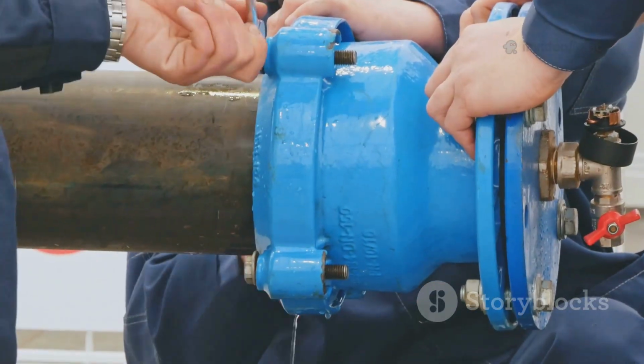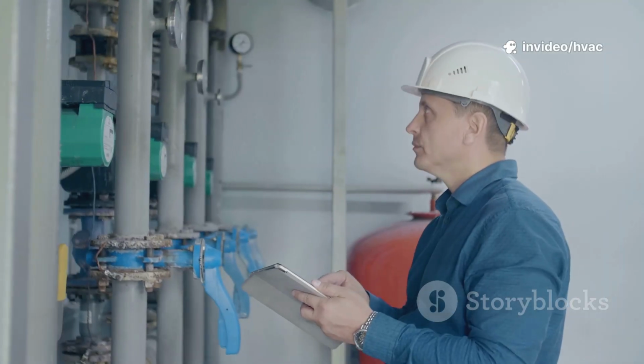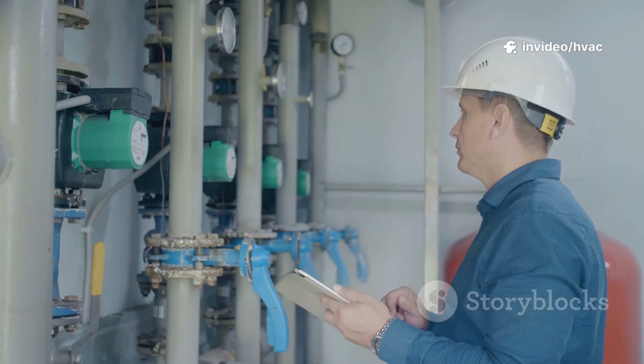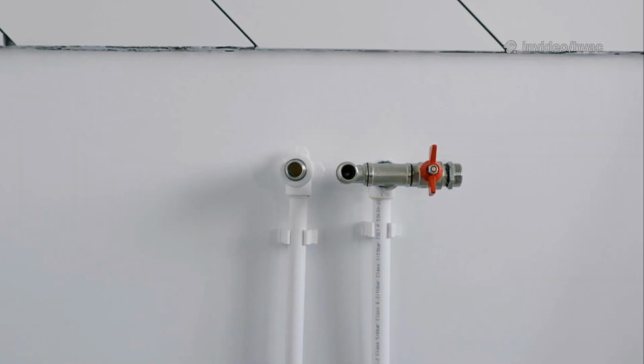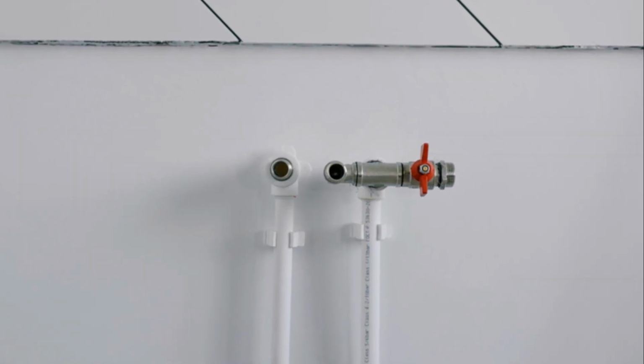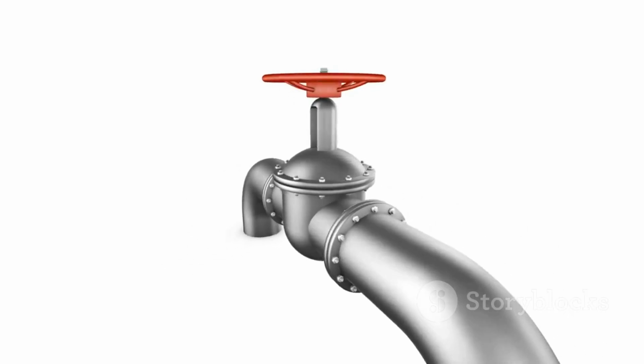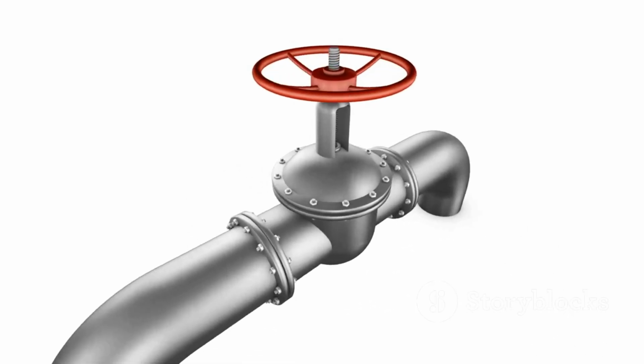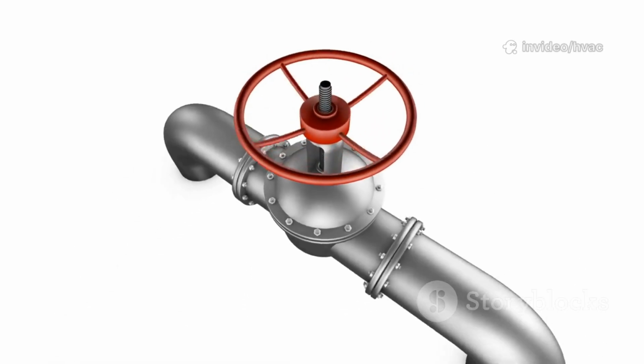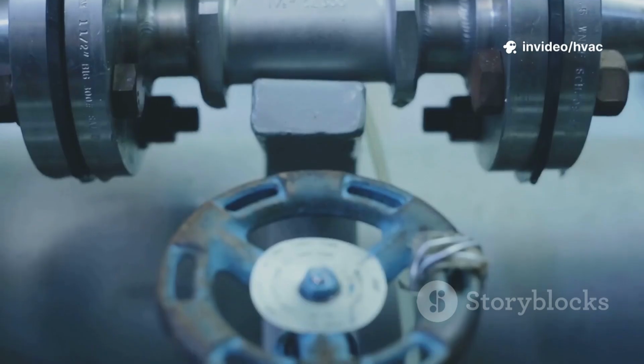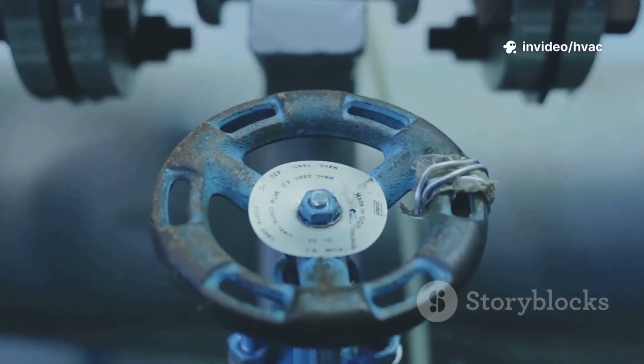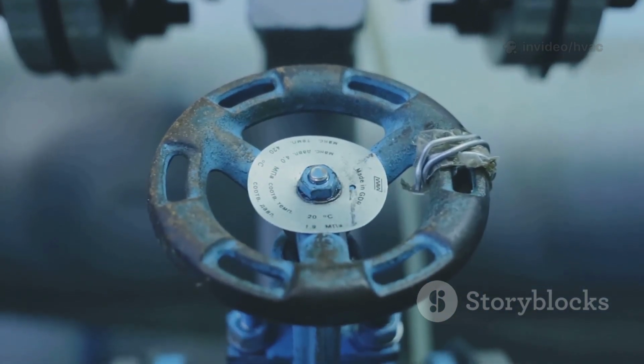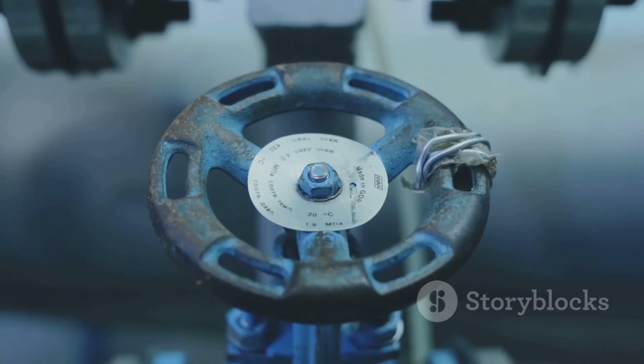With PICVs, this is not necessary. You should select the valve based on the required flow rate, not the pipe size. Often, the correctly sized PICV will be smaller than the connecting pipe. For example, a terminal unit connected with 1-inch pipe might only require a 3/4 inch PICV to achieve the desired flow rate. Using a valve that is too large for the required flow will result in poor control, as small movements of the actuator will cause large changes in flow.